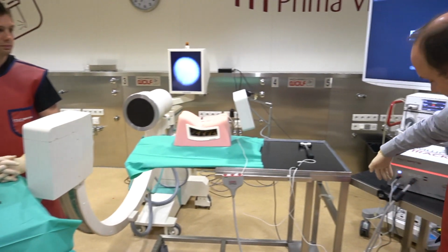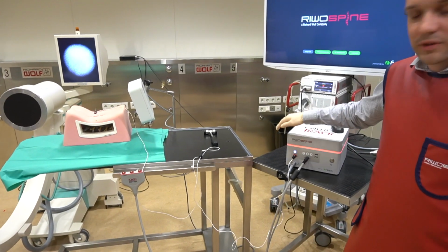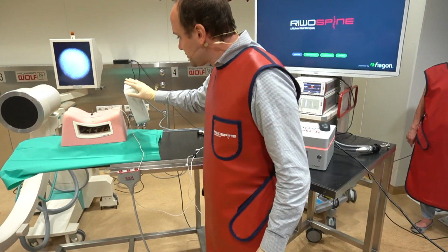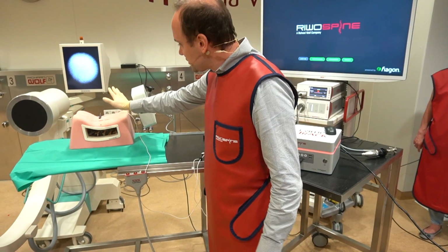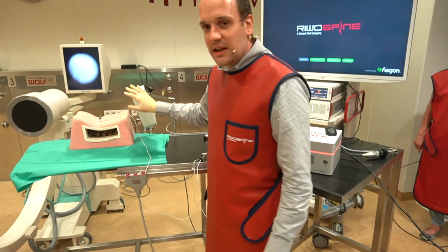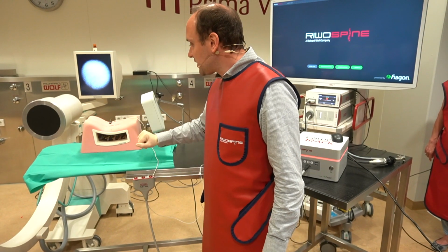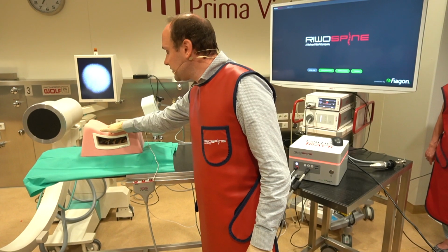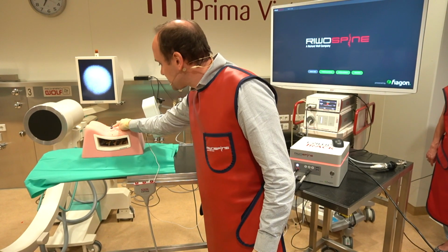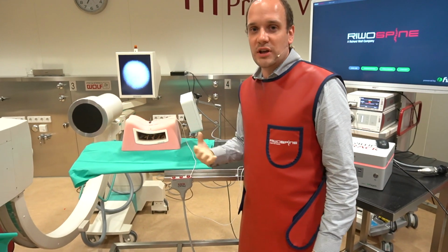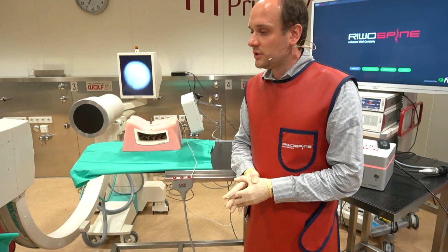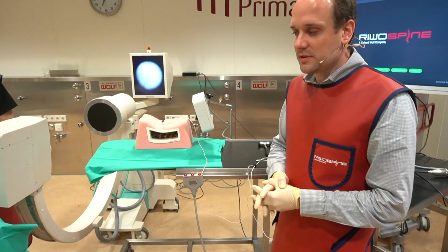So the field generator is connected here on the left lower edge of the cube 4D. And it goes here to the sacrum of the patient, just a little bit over the patient. It emits electromagnetic fields, which then can be tracked by the sensors that we have in the field, such as the patient reference, which we connected here on the K-wire, but also the other sensors that I will show to you just in a second, and as well as the mapper bridge.